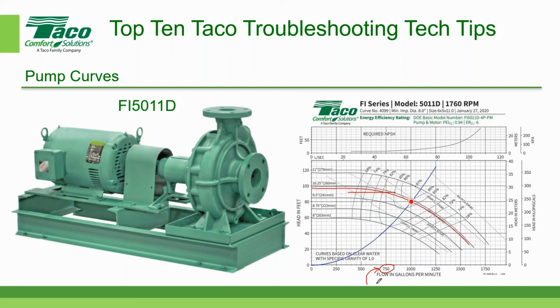Now let's assume for a moment that their field data was correct, and that they're actually getting 750 gallons per minute. But the pressure differential across the pump is 92 feet instead of 80 feet. So now we have a problem. Initially, the customer may have thought that we have a problem with the pump, but in reality, it's starting to look like there is a system issue somewhere, because we are actually operating on the pump curve, but at a different pressure drop.